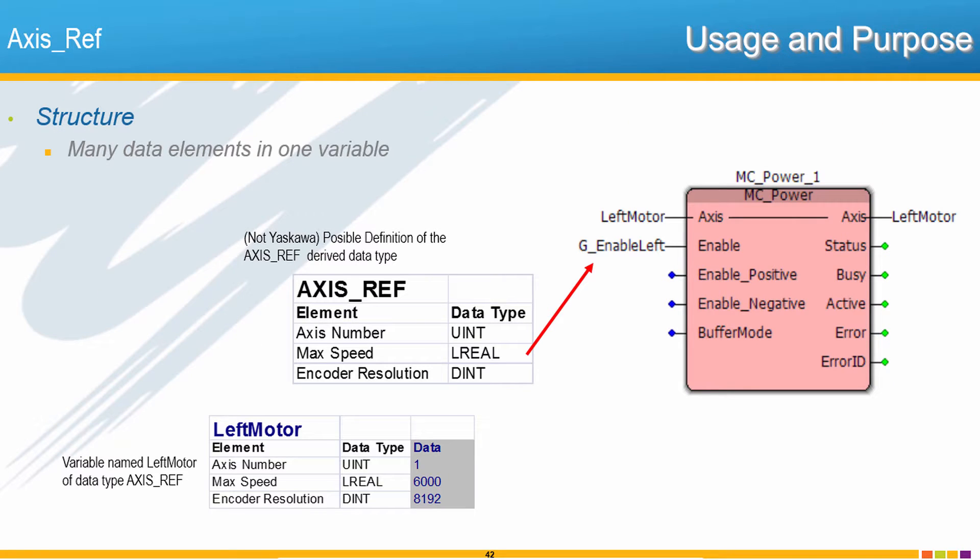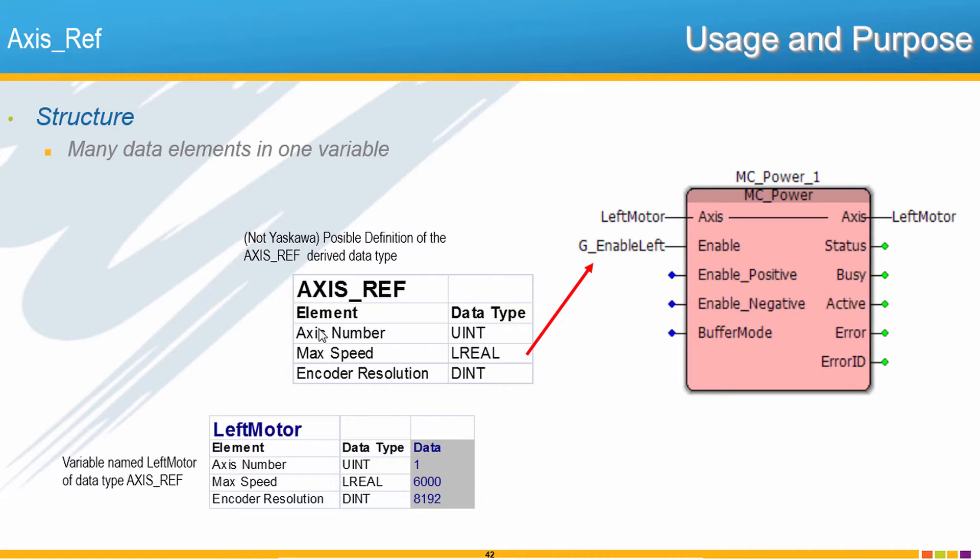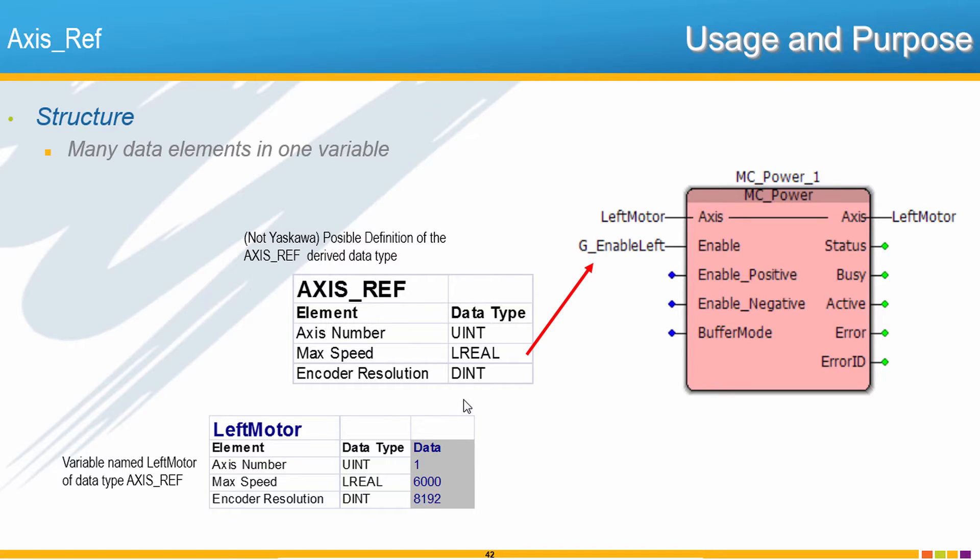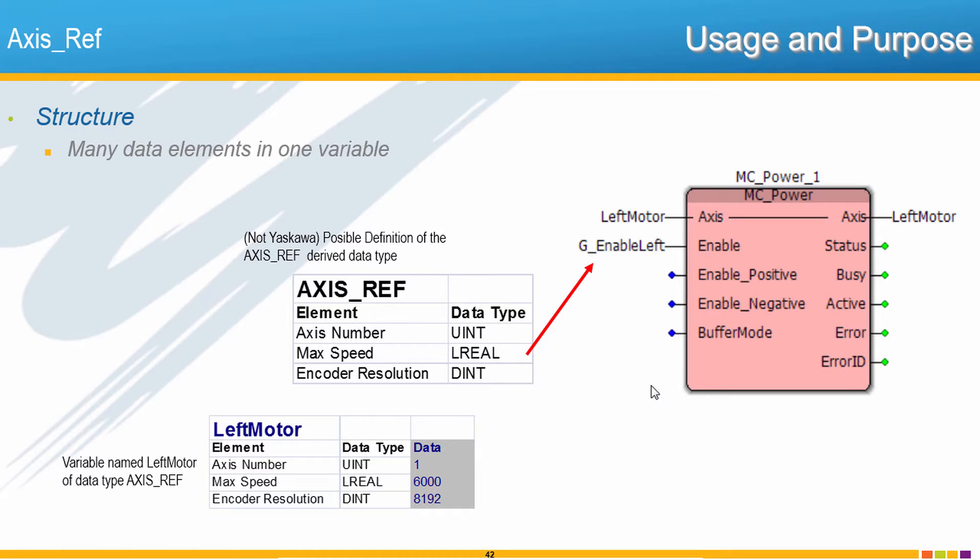The axisRef data type definition is not defined by PLCopen because of the hardware specific data that it can contain. So instead, each vendor defines their own axisRef structure. This way, through one axisRef variable, all axis specific information such as the axis number, maximum speed, encoder resolution, or user units can be referenced by the PLCopen function blocks through this variable. So each block just takes whatever data it needs from the axisRef to operate that axis correctly.